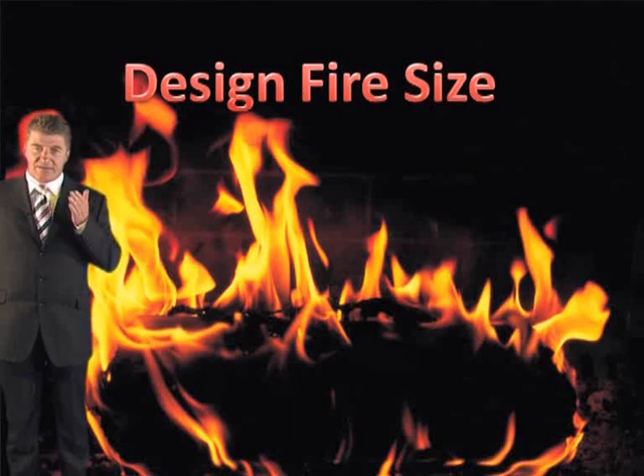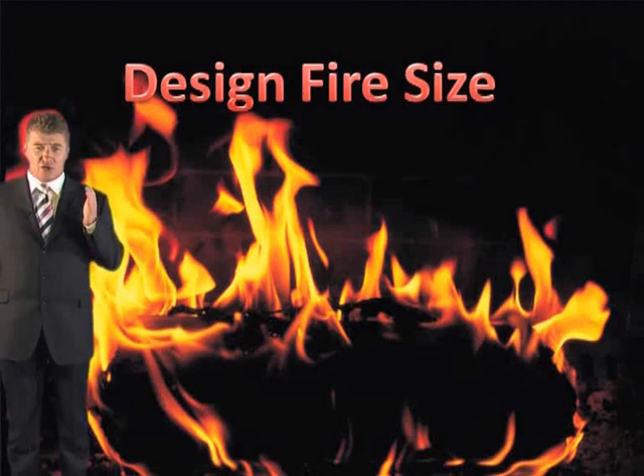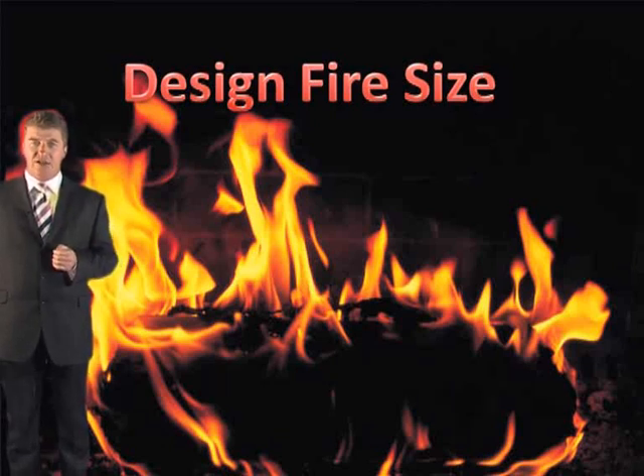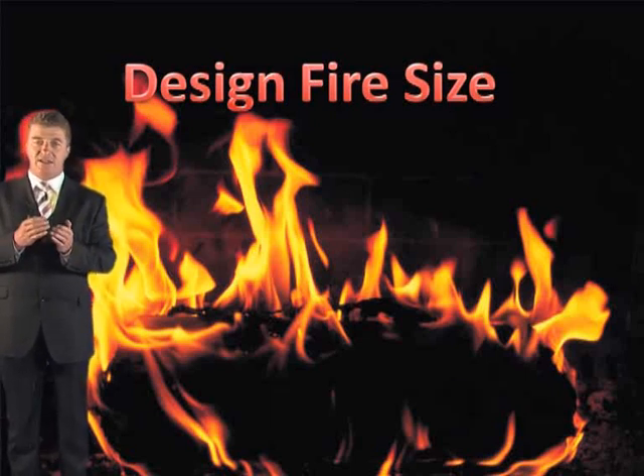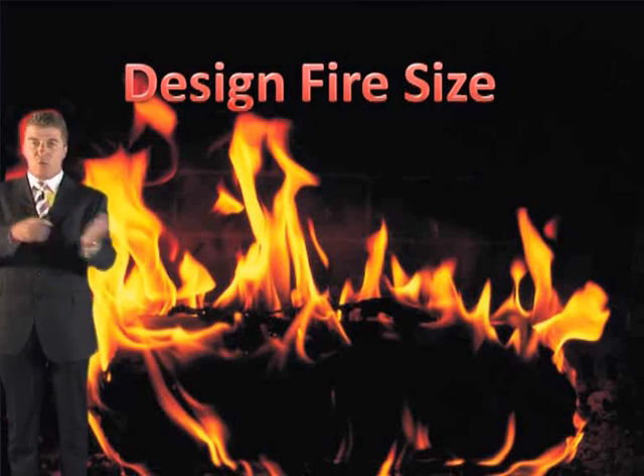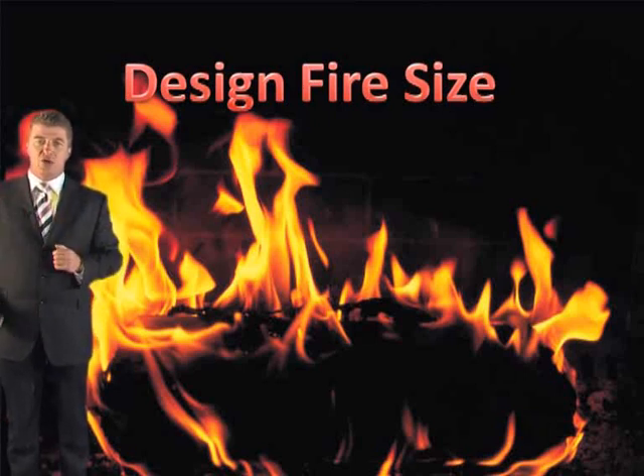S is your design fire size. In this step, you need to determine the fire size that you're going to adopt in all your calculations. And this is a critical stage, because if you get this wrong, the wrong design fire size means the whole system will fail. In this step, you might identify there's a number of different scenarios, and you might have to work out different fire sizes. You might have one that's a complex plume, one that's a simple plume. So you might have different design fire sizes. That's what we're going to go through, how you work it out.